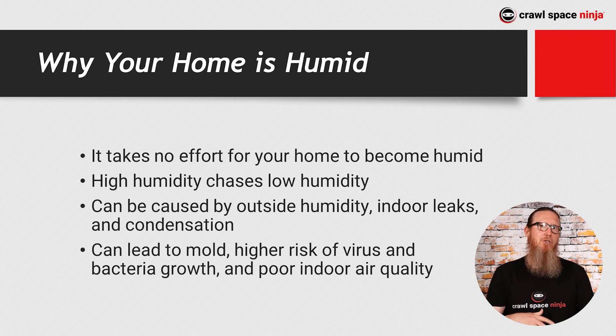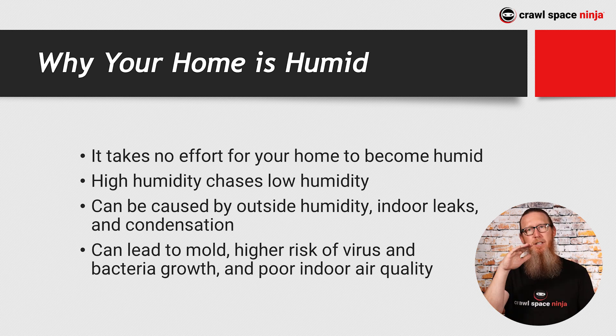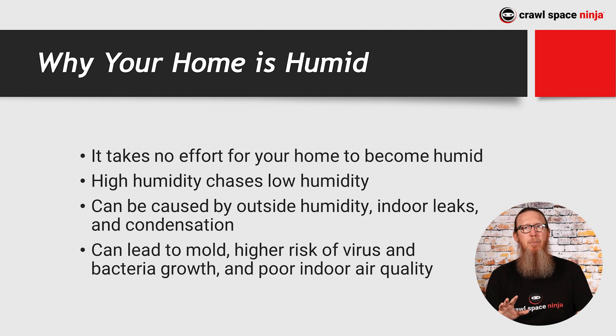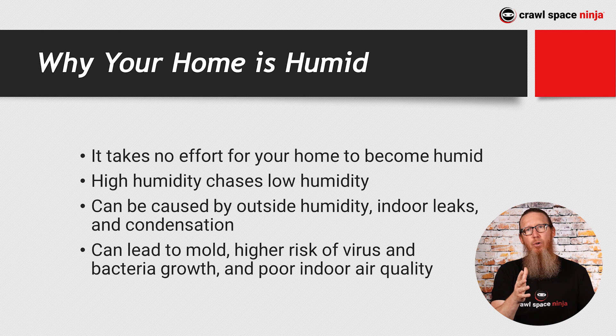Why is your home humid in the first place? As your AC runs, part of the job of the air conditioning system is to lower humidity. If you're in a humid area like Tennessee where it's 95 degrees, that outdoor humidity at 80% wants to drive itself into the house where AC has lowered it to 40% — similar to how the high chases the low on weather maps. Also, your home leaks; you may have plumbing issues, a wet crawl space, and condensation where hot humid air hits cold ductwork and causes humidity to spike.